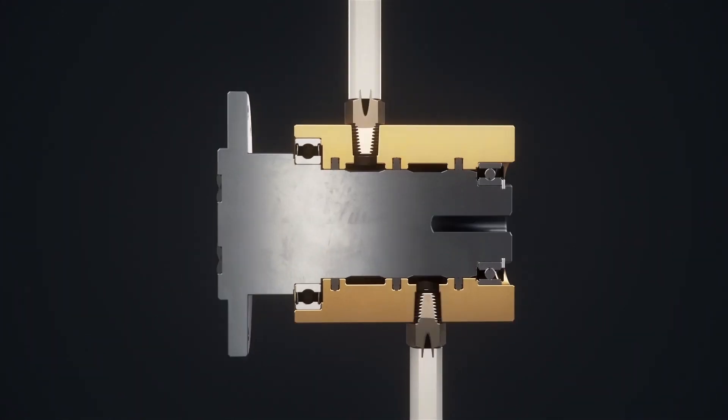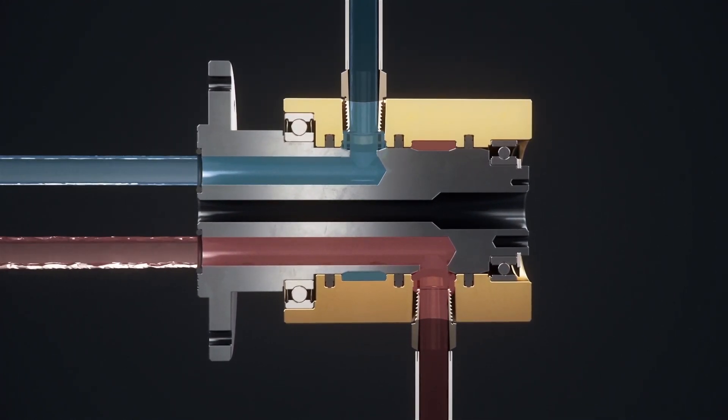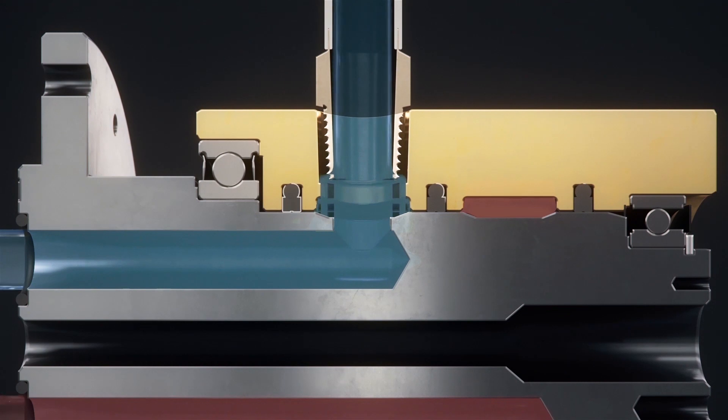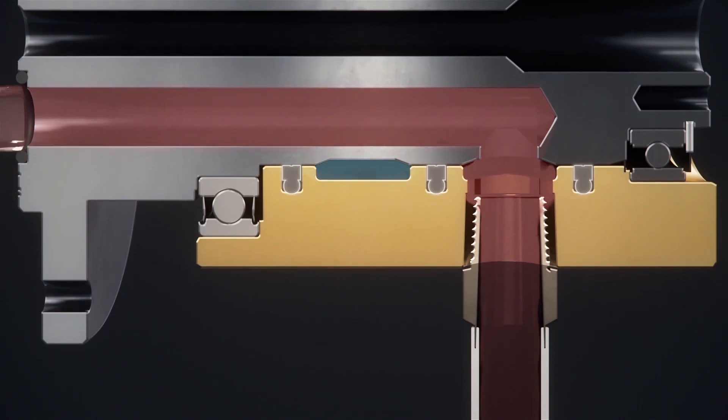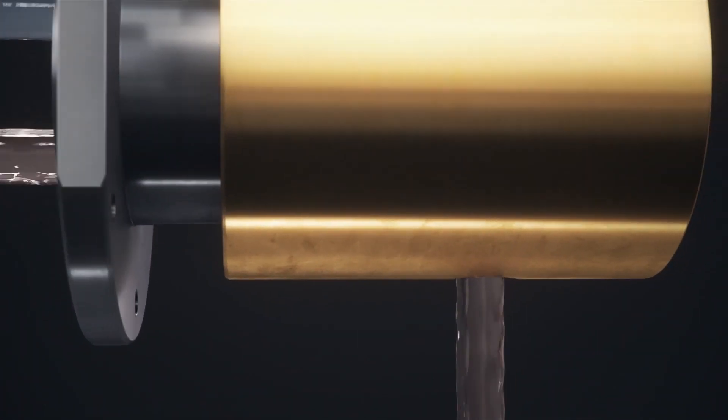To create the passages, each port on the housing is aligned with a channel in the rotor. Media separation is maintained using seals between the housing and rotor. The sealing technology utilized is the most important factor in multipass rotary union performance.